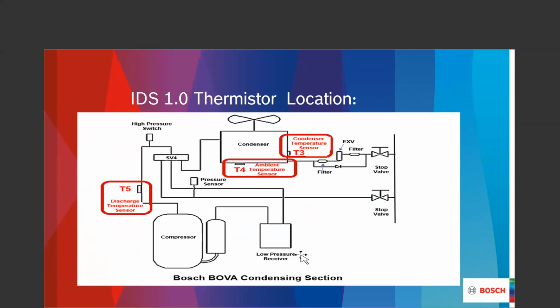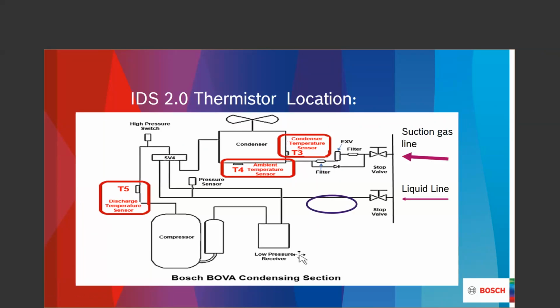Anytime that I had L1 and L2 powered to the unit and the unit was not on, what we would call a standby situation, I should be reading the ambient temperature that is located there where the condensing unit is sitting. So this is the 1.0. When the 2.0 came out, we added a sensor on the liquid line, and that sensor is called T3L. And it is a great add. It's a great upgrade.